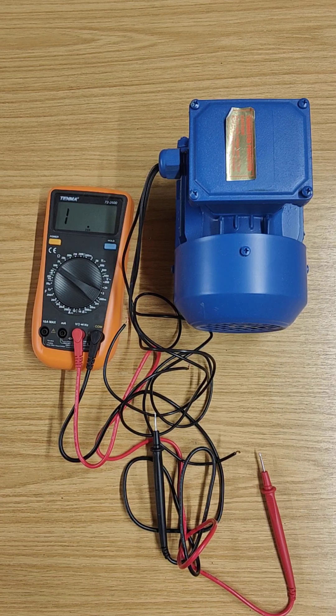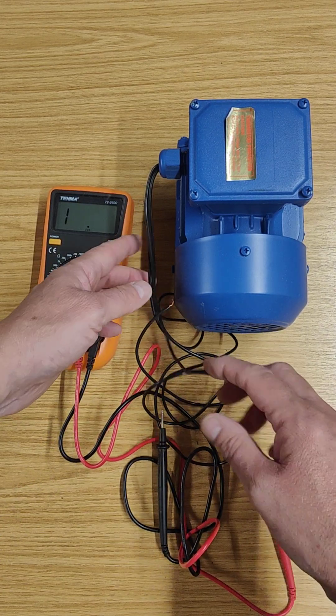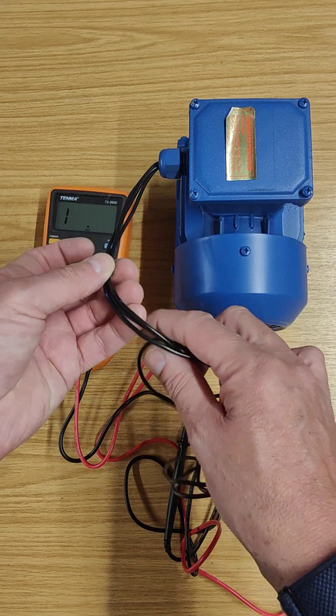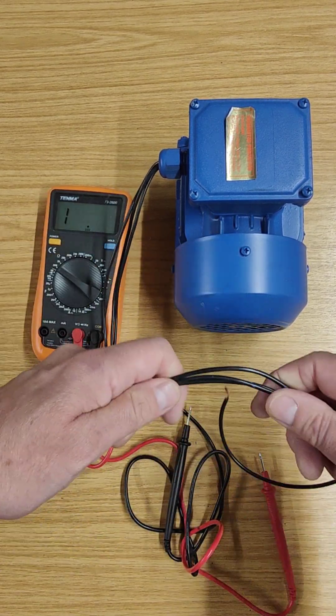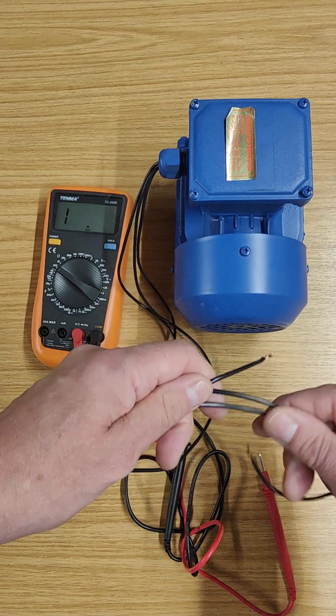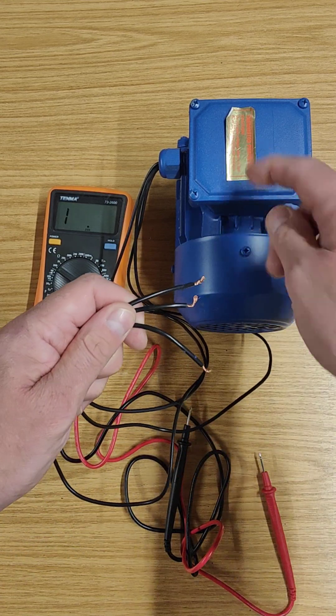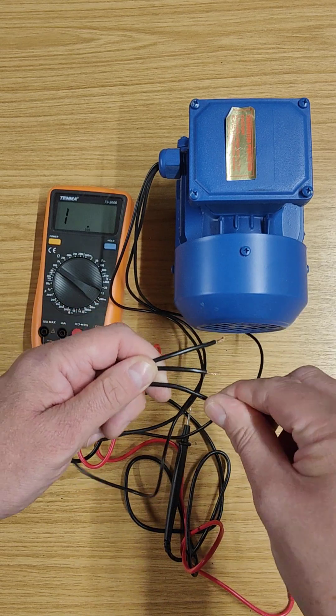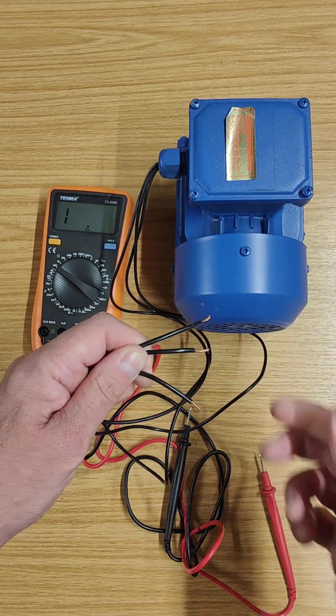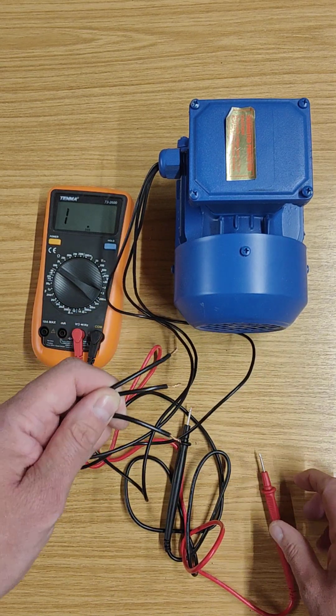I'm going to show you the tests that you can do if you have a three-phase AC motor. If it's an AC motor treadmill, you will have three wires rather like these here, connected straight into the motor to the terminals inside. You'll have perhaps connectors on the end on the actual machine that you're testing, but the principle of what I'm going to show you is the same.